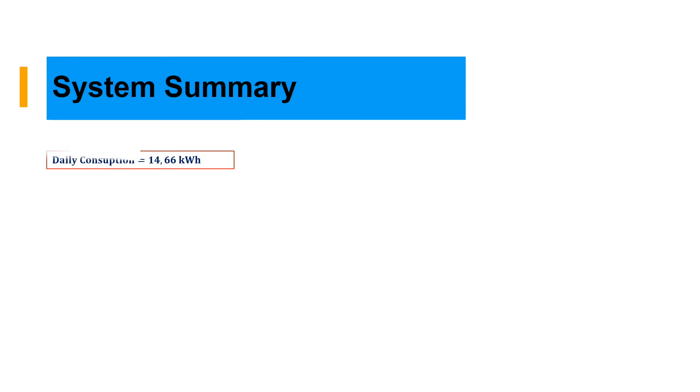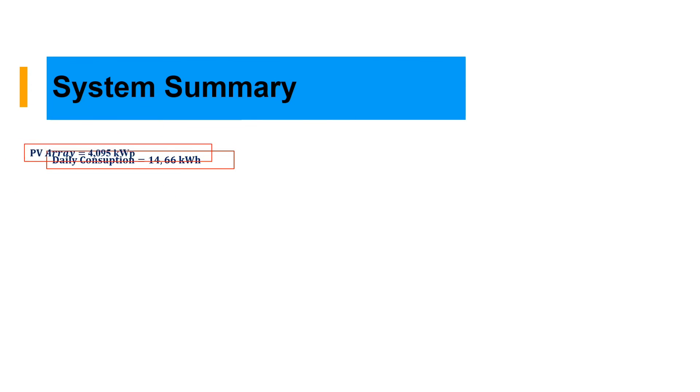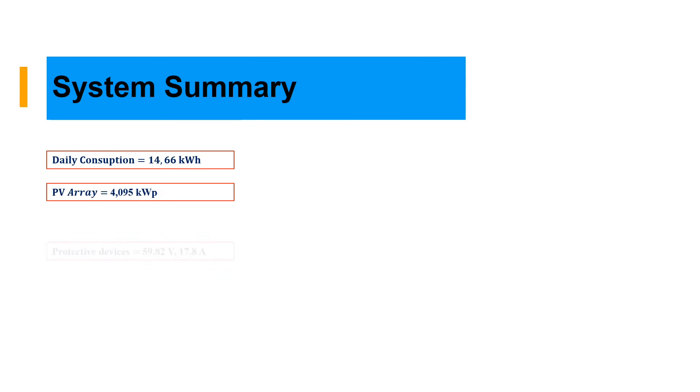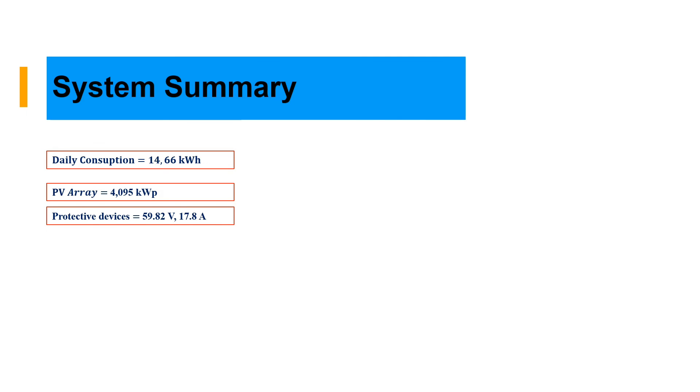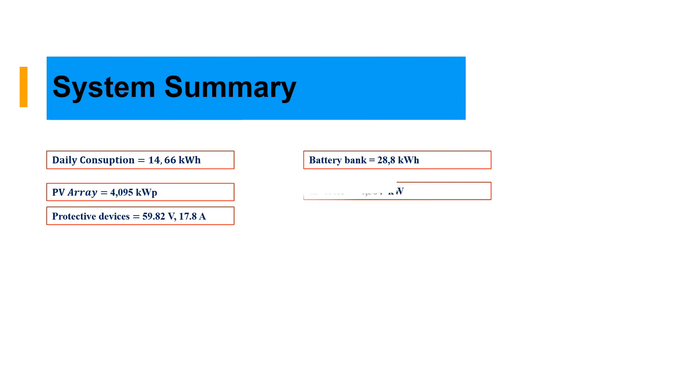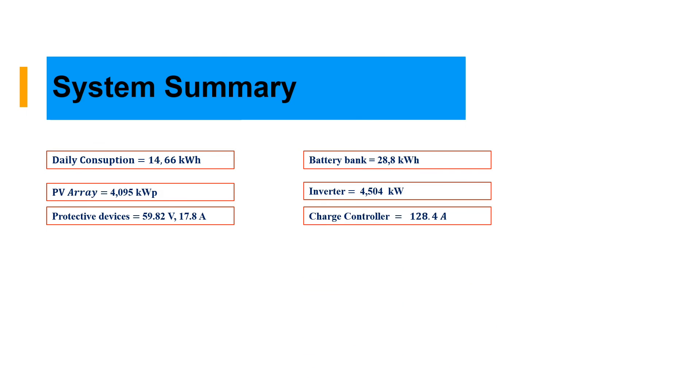As a summary of the system, the daily consumption is 14.66 kilowatt hour. PV array equals 4.095 kilowatt peak. Protective device should be 59.8 voltage or 17.8 ampere, that is the minimum. Battery bank is 28.8 kilowatt hour, which could supply for two days without interruption. Inverter size is 4.504 kilowatt. Charge controllers is 128.4 ampere.